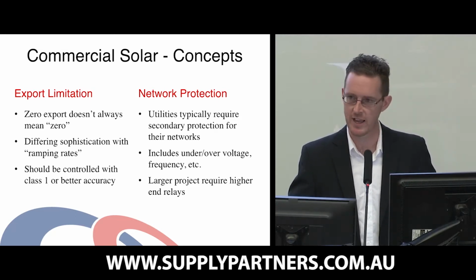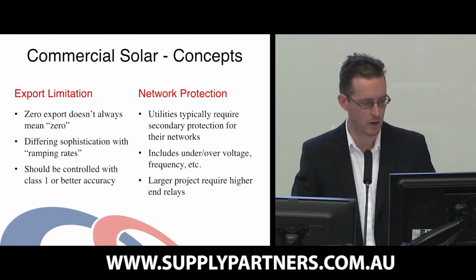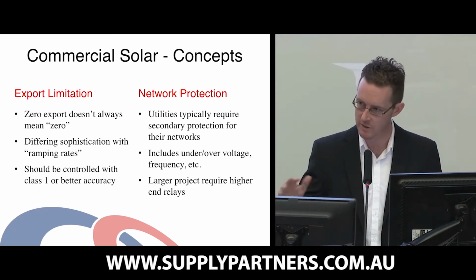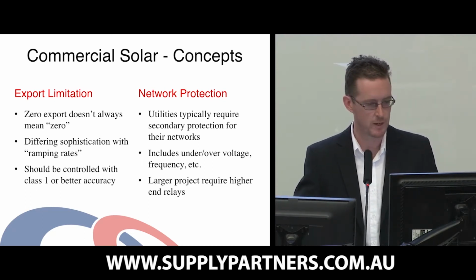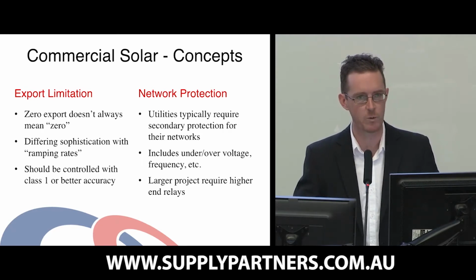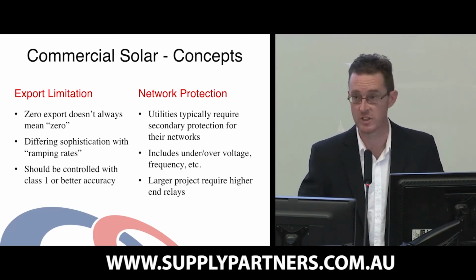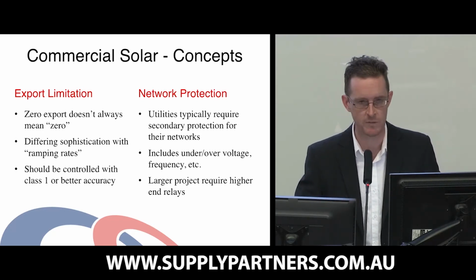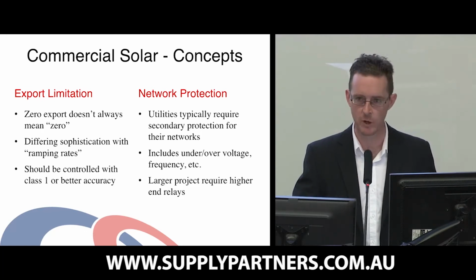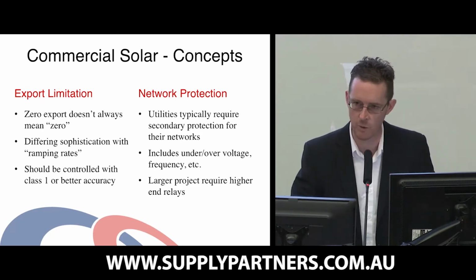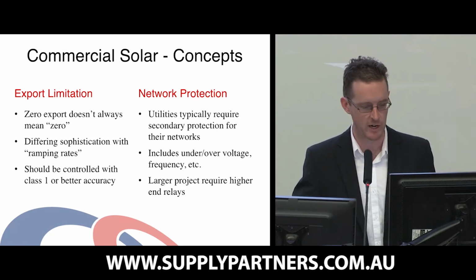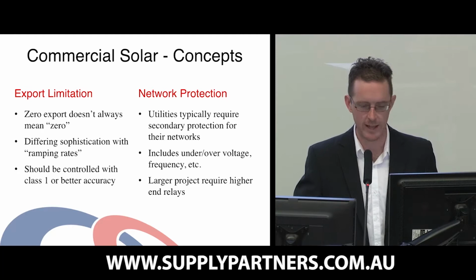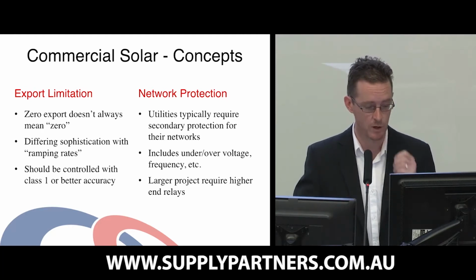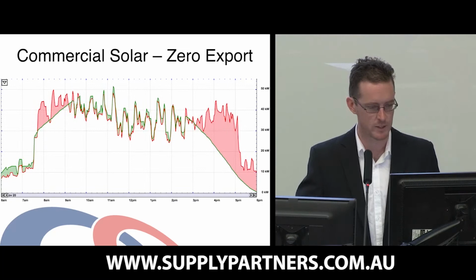Ramping rates, this is just how smoothly we can increase or decrease the inverter's output to match the load. You want the smallest steps and the smoothest operation as possible. And then network protection. Systems over 30 kilowatts, utilities say, well, look, we understand that your inverters will turn off if the voltage is too high or too low, or the frequency is out of range, et cetera, but our grid is worth a lot of money to us, and we want to protect it, so we want you to install secondary protection. And when you get into the really big projects, the megawatt style, then the requirements around this really ramp up.